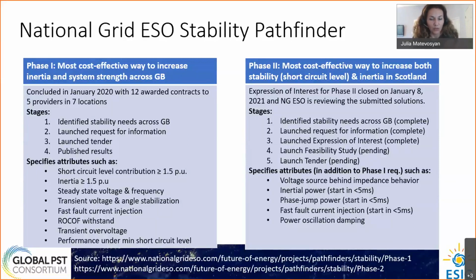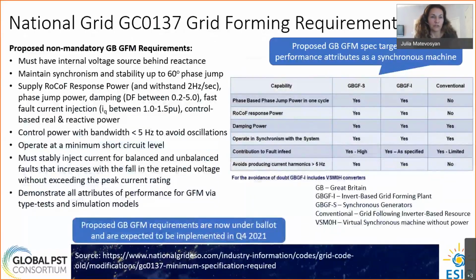So during this time, when the first phase of Stability Pathfinder was already going on, an expert group was formed that worked on minimum specifications for, initially it was called virtual synchronous machines, but then they expanded it, and now it's called grid forming inverters. This group developed minimum technical specifications for grid forming inverters.